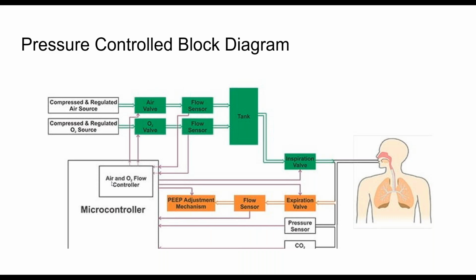But this does have a couple of components that we talked about, those flow sensors. There are flow sensors in some ventilators on the intake systems and pressure sometimes of the compressed gases or your wall outlet, middle of the screen. There's a flow sensor typically at the exhalation side of the patient. That flow sensor looks for normal conditions of flow, and there will be typically something for a cough so that a patient can cough on their own when they need to cough. They can force more flow through a normally restricted space because there's a sudden need to cough.